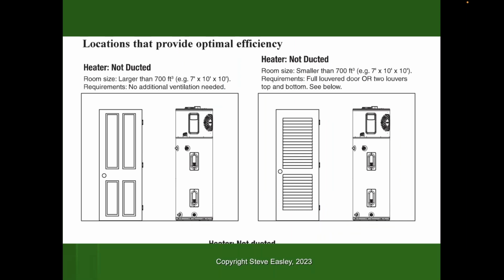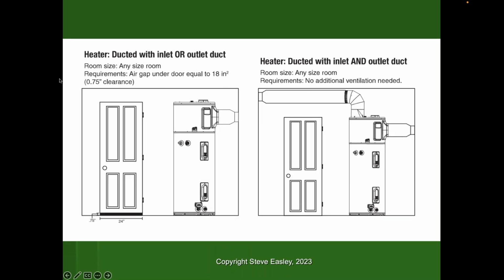It is important to recognize that if you're putting one of these inside your house, you need to have a room that's roughly 700 cubic feet. So that's roughly 7 by 10 by 10, and you can have a door on it, but you need to have enough space so this thing can breathe and extract the heat. You could do louver doors, that would certainly help. Or you could duct the system. They make these to where you can actually duct to the outdoors or duct to the indoors and bring fresh air in. You can undercut.